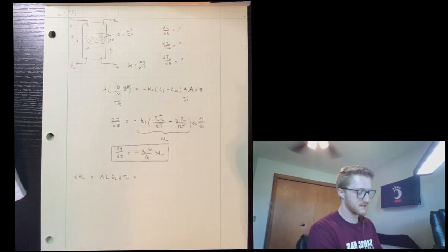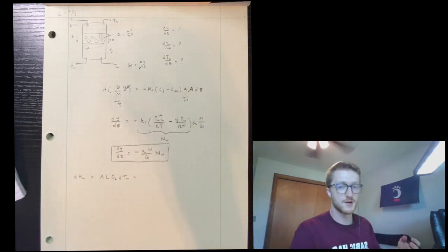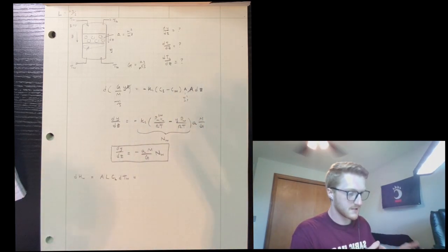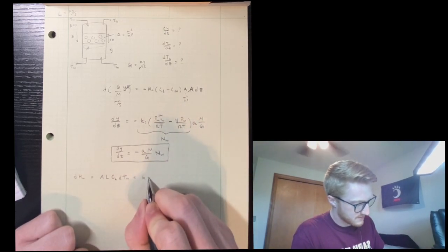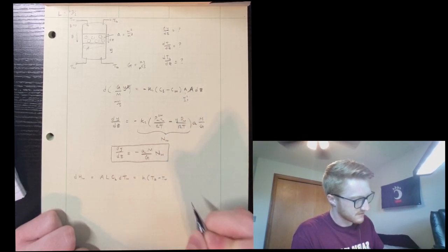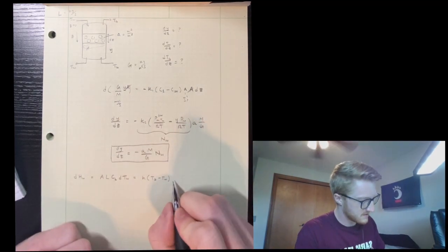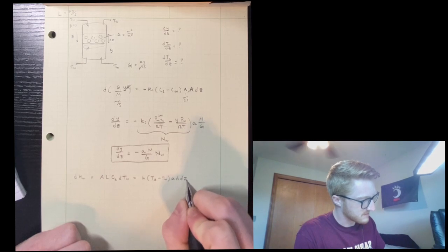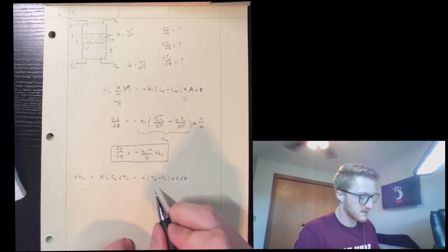And we want to look at what causes this change in the temperature. We know that there's going to be heat from the air going to the water, and we also know that there's going to be evaporation causing this change in the temperature. So we can look first at the heat coming from the air to the water. We're going to have some heat transfer coefficient, H, times the temperature driving force from the air, or the gas, to the water. And then we also have to include that area difference. So we'll call that the specific area of the packing times the cross-sectional area times the change in the height. That will give you your volume times your specific area, and that will give you your heat transfer per area.